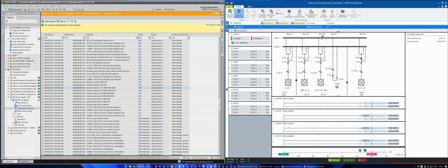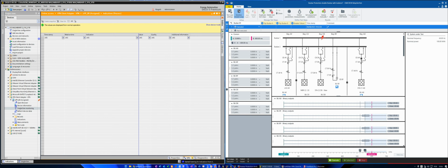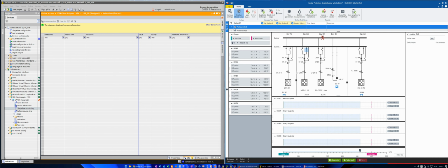So now what I want to show to you, I want to show if I change a bay connection to another bus bar protection, I can test this one. So let's do this. I will clear this event, and now we change this bay and I have to clear the results. Now I will change this bay and put this bay in bus bar protection 2, and I just give the fault in bus bar 1. So let's do the play.